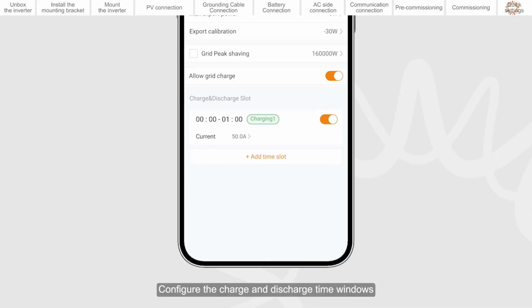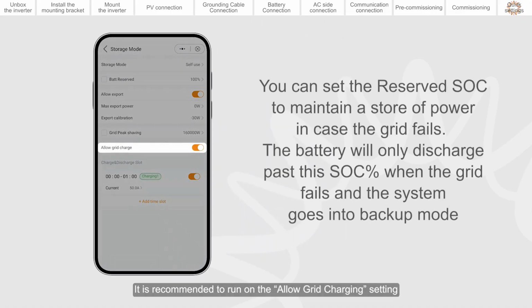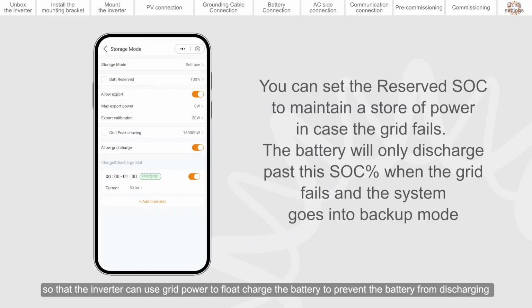Configure the charge and discharge time windows. Be sure there is no overlap between the windows. It is recommended to run on the Allow Grid Charging setting so that the inverter can use grid power to charge the battery to prevent the battery from discharging past the safe level.